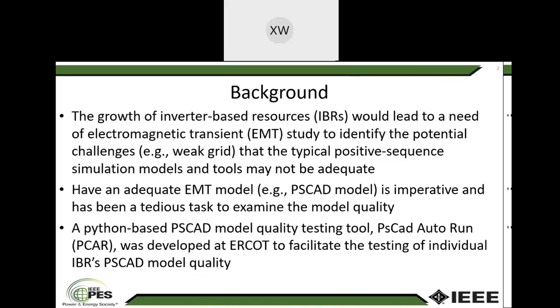Background: the growth of inverter-based resources leads to a need for EMT studies to identify potential challenges, for example, weak grid issues, that the typical positive sequence models and tools may not be adequate for. Having an adequate EMT model, for example, a PSCAD model, is imperative, and examining the model quality has been a tedious task. A Python-based PSCAD model quality testing tool named PCAR was developed at ERCOT to facilitate testing the PSCAD model quality of individual IBRs.